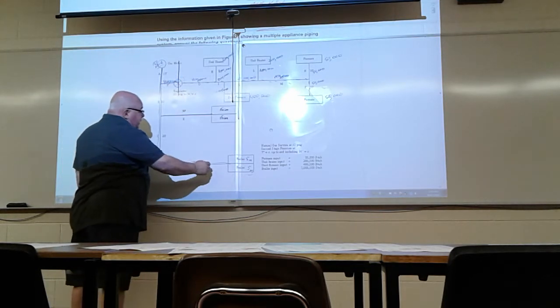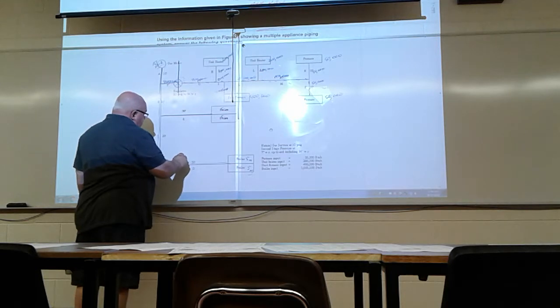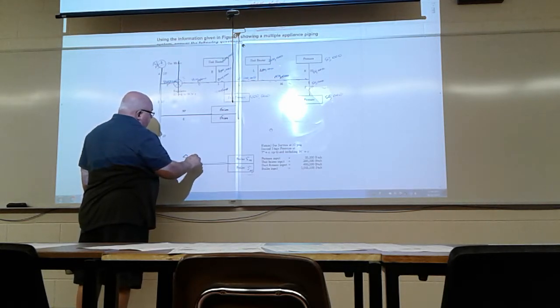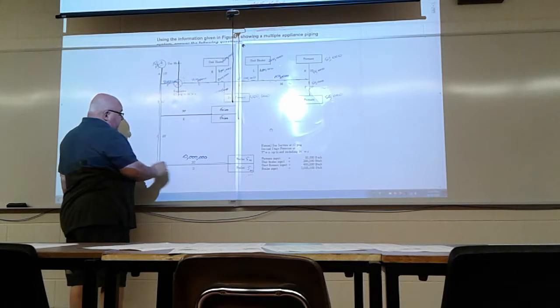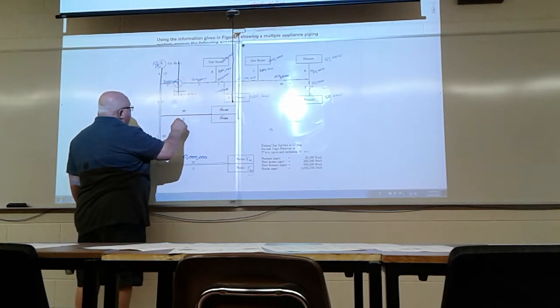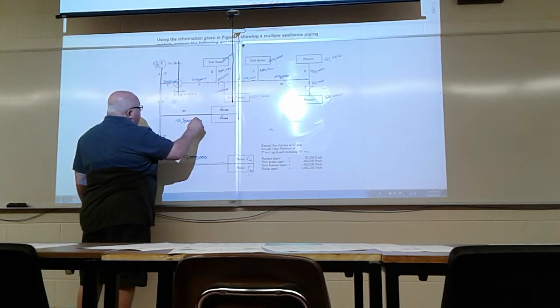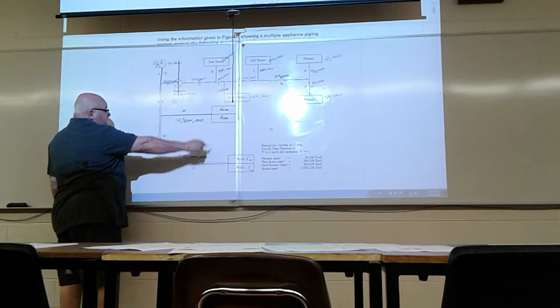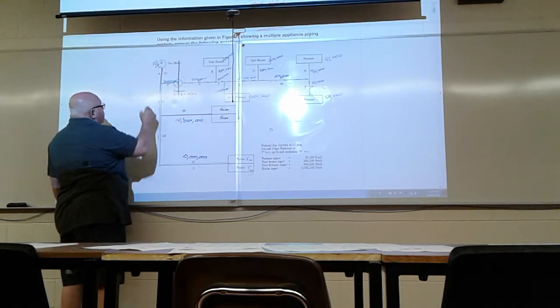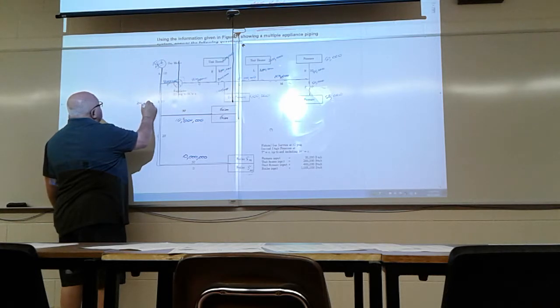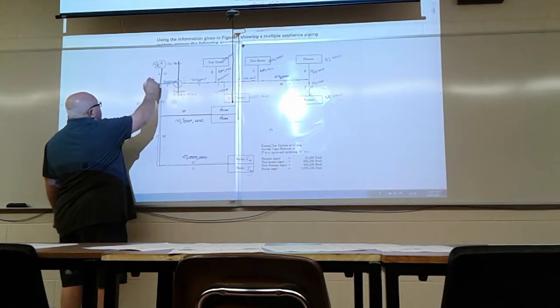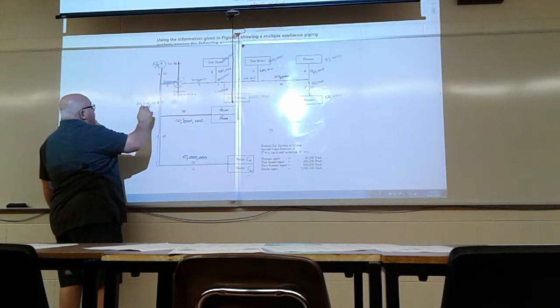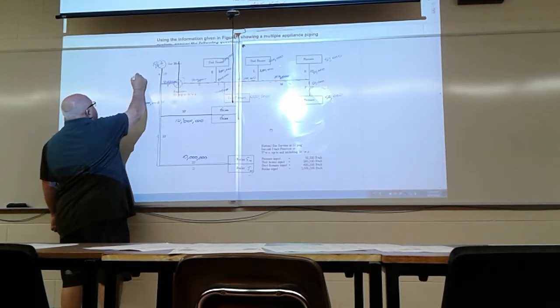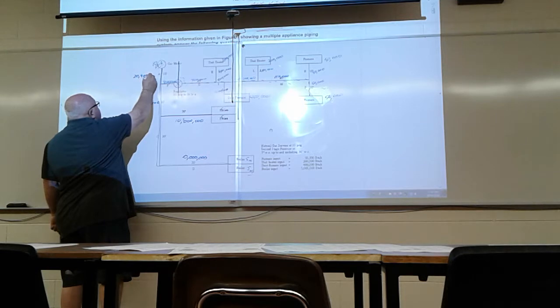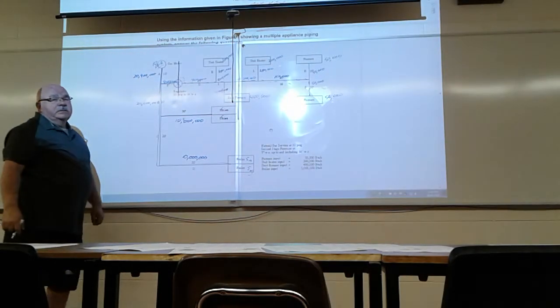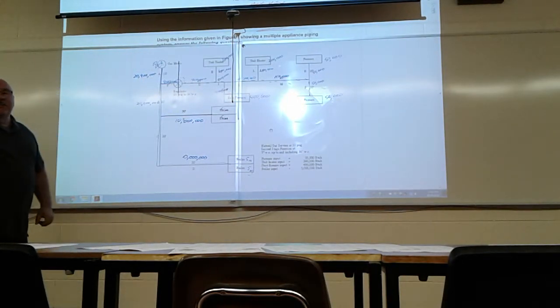I'm going to start down here because it's easy, 5 mil and 10 mil, or 5 mil and 5 mil is 10 million BTUs. Okay, so pipe C and D, pipe E is going to be the same thing, 10 million BTUs. Okay, and pipe B has to handle all the high pressure boilers, so that's going to be 20 million. Okay, and pipe A has to supply gas to everything, so it's 20 million plus 900,000, so 20 million, 900,000. Okay, everybody good? Okay, only took me maybe a minute and a half to do that.